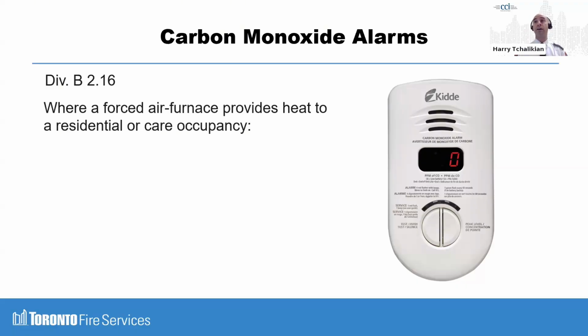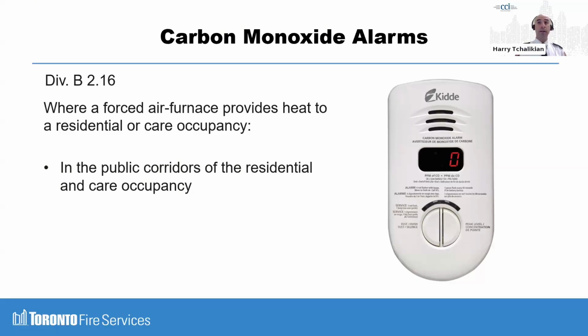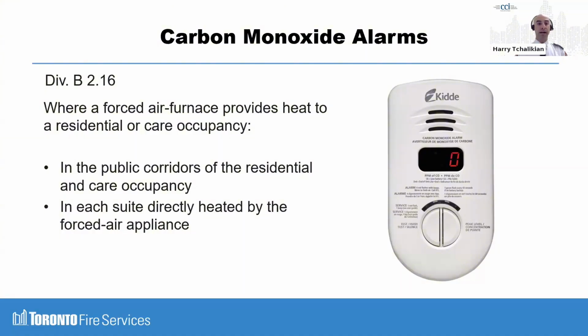Next, where a forced air furnace provides heat to a residential or care occupancy, you need a carbon monoxide alarm in public corridors of the residential and care occupancy, and in each suite directly heated by the forced air fuel burning appliance. And so this is a hot topic. I'll go into detail for this. First of all, for the public corridor, it's one detector for every 25 meters of corridor. And then any suite that gets hot air that originated from a fuel-fired appliance, those suites in a residential and suites of a care occupancy also need carbon monoxide. And so I want to go over an actual floor plan. So let's look at some of these requirements directly applied.